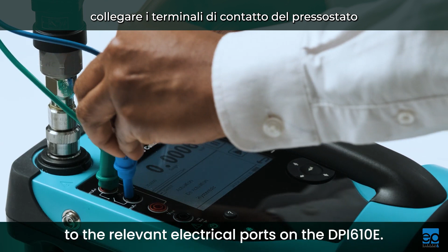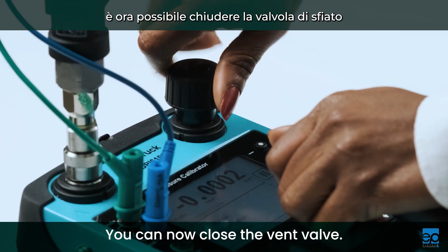On the calibrator screen, the pressure is indicated in channel 1, while the switch test details are displayed on channel 2. At this point, the contact state is detected and will be displayed as a normally open switch with the NO icon or a normally closed switch with the NC icon. The switch I have here is an NC switch, which means that in normal pressure operating conditions, its state is closed. You can now close the vent valve.